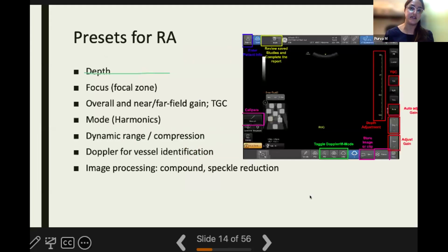So like I mentioned, either you can set the preset by the modes that are already present in your ultrasound machine. A lot of them even have further sub-demarcations where we can choose for shoulder, knee, and other different parts of the body. Or we can actually, once we have kept the probe onto the patient, change the presets on our own and change all of these settings one by one to gain the best possible image and to assist needling and performing a nerve block.